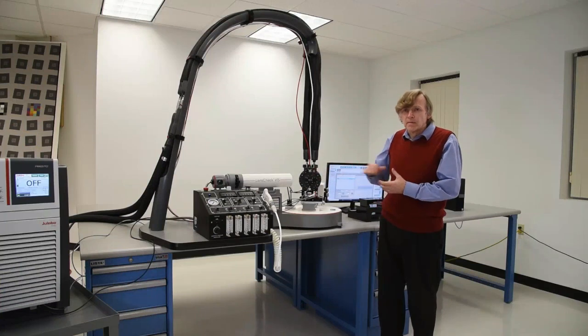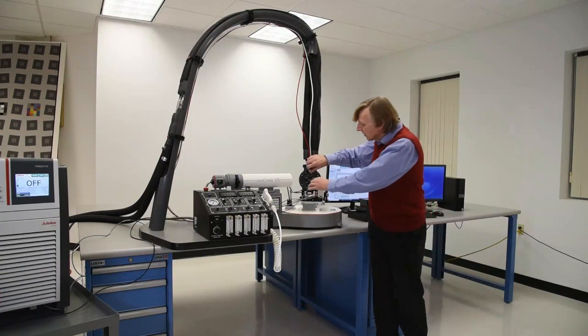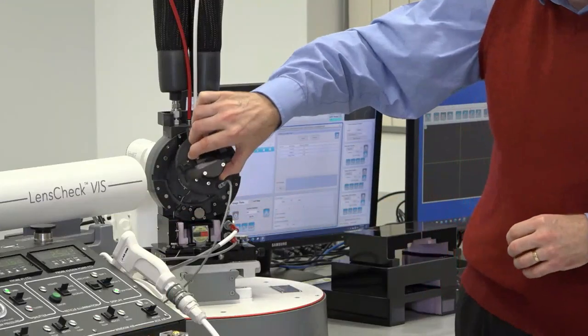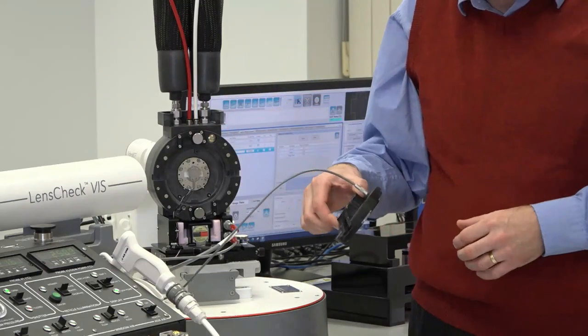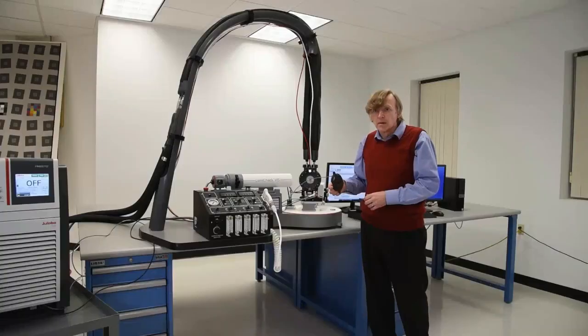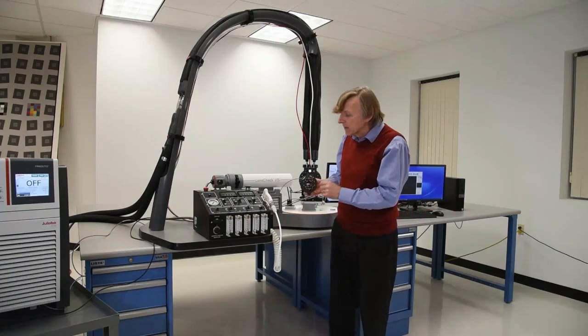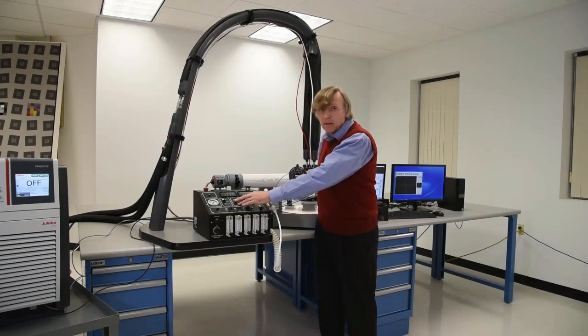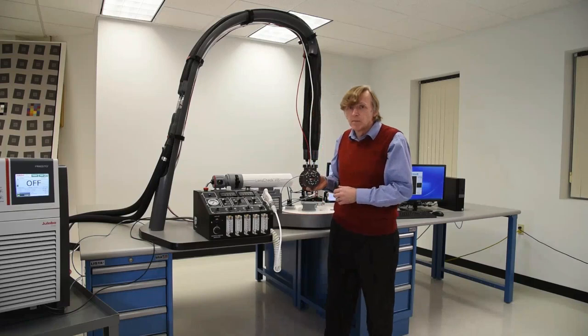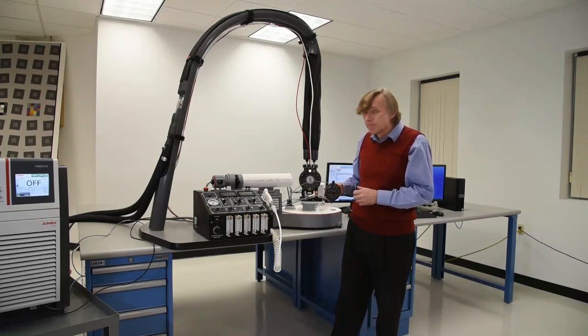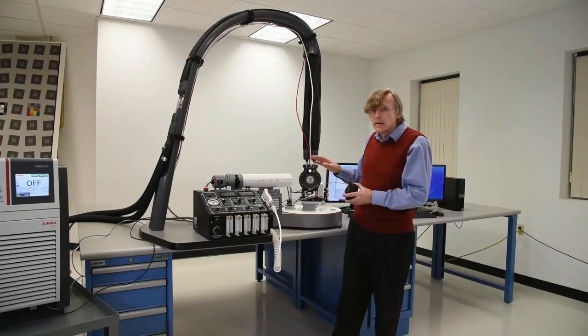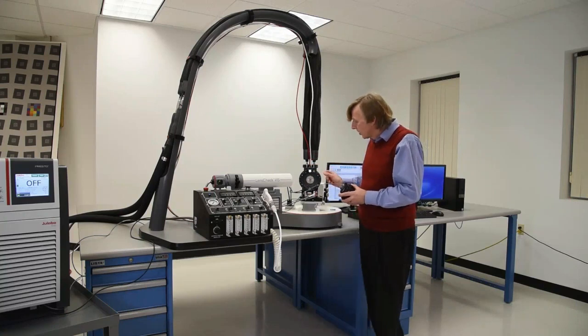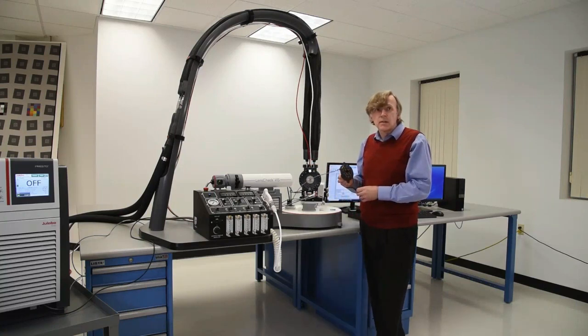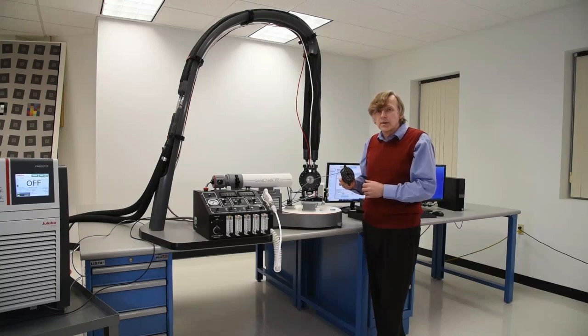The lens is installed through the front of the chamber by first removing the window assembly. This has a simple bayonet-style latching mechanism, but you will notice that there is a cable attached to the window. This is used to control the brightness of LEDs that are used to illuminate the interior of the chamber. We shall discuss their purpose shortly. The TC1010 has 2 defining characteristics: the shortness of the chamber and the construction of the front window. Together they ensure that the entrance pupil of the lens under test can see the widest possible field of view.